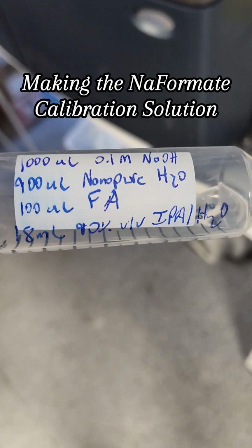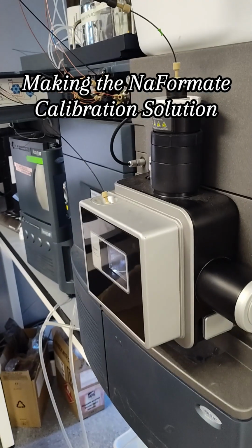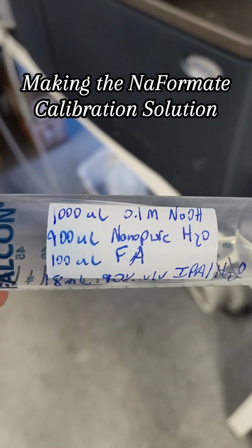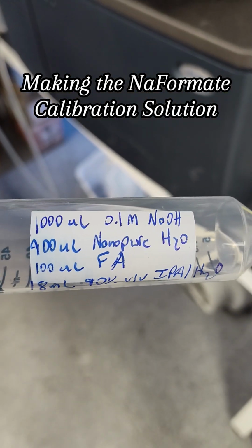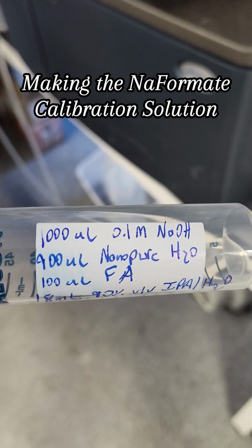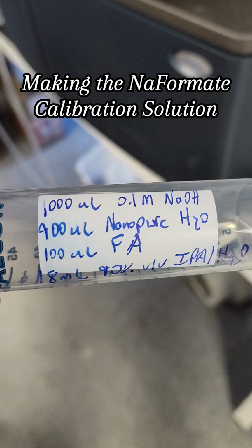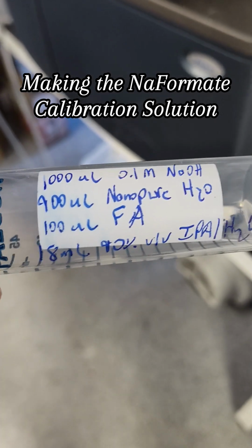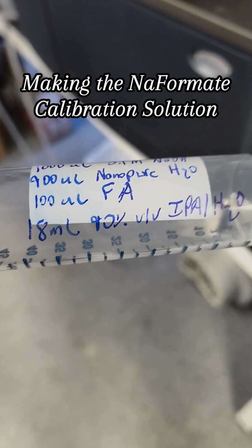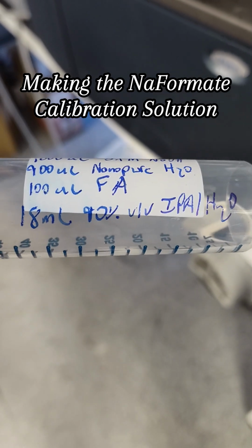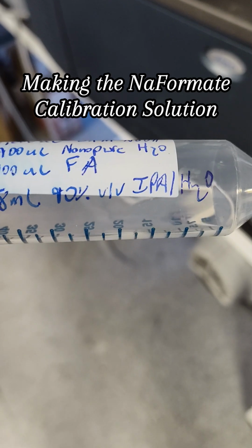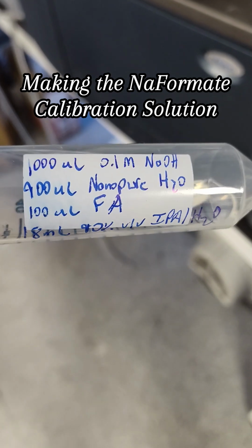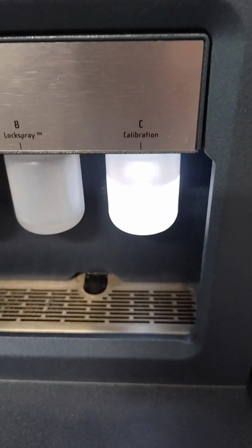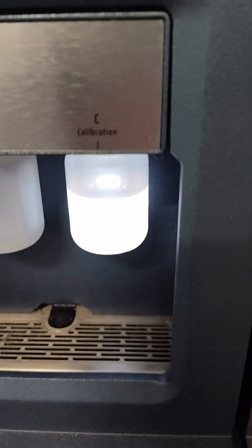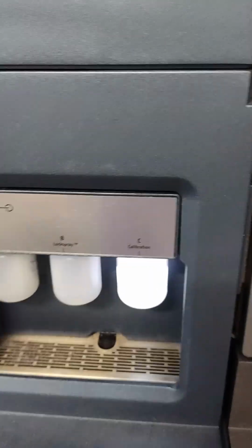So we're making sodium formate for calibration of the Xevo QTOF. This is the exact formulation that we're doing: 1 mil of 0.1 molar sodium hydroxide, 900 microliters of water, 100 microliters of straight formic acid, high grade, and then 18 mils of 90% isopropanol water. And that we put directly into the C. I guess that makes up just enough to fill up the calibration C bottle on the instrument.